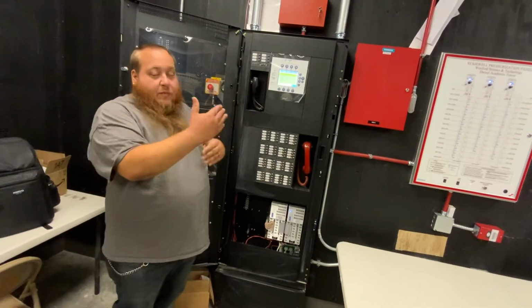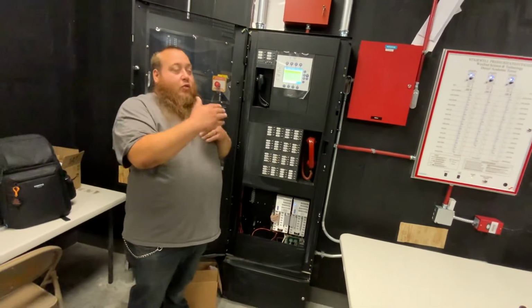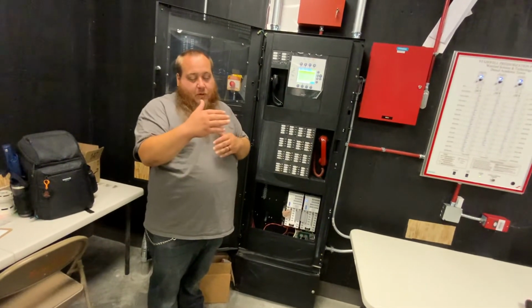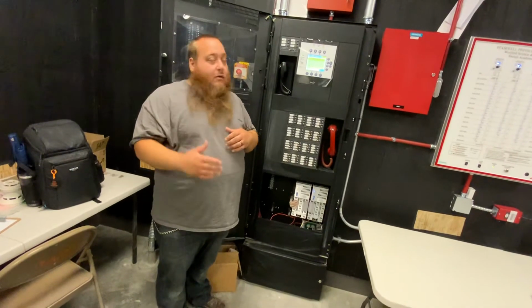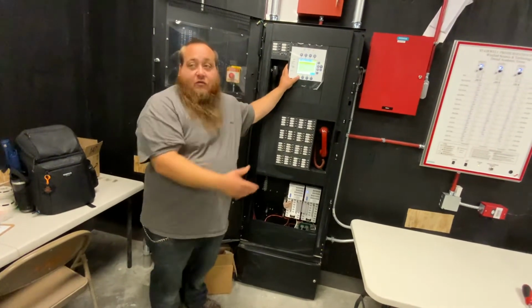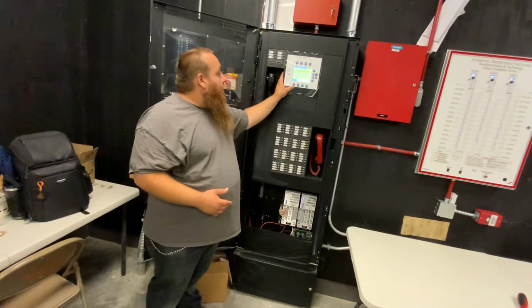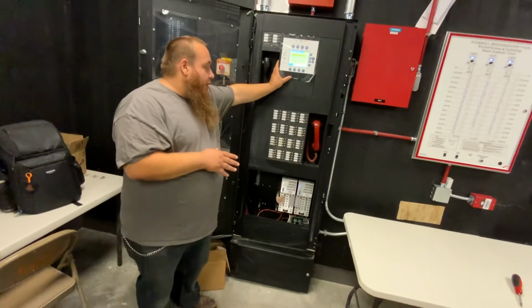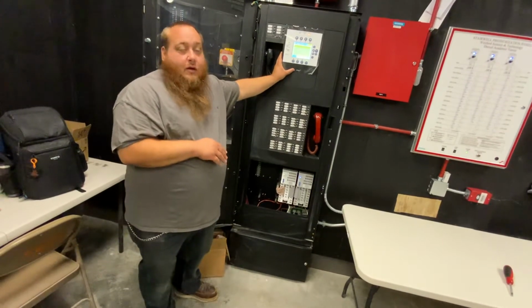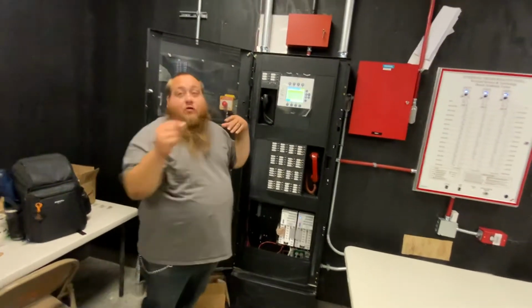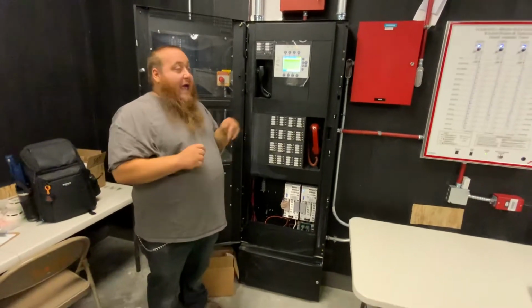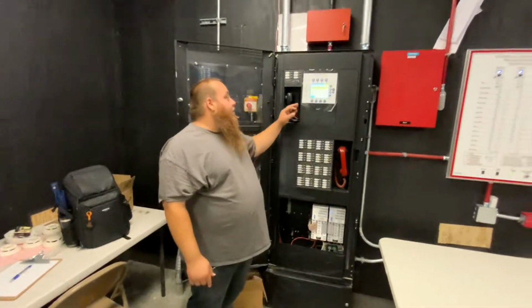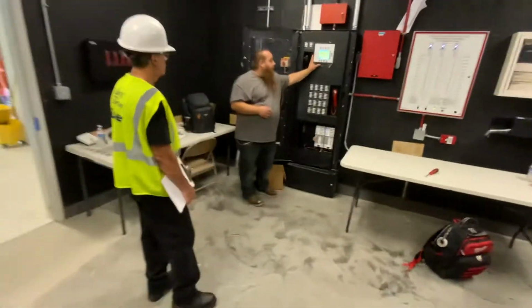Just in case you want to keep a pattern of, say, a ground fault, every time a door opens up, it hits a wire. It's easier to keep a pattern that way when you know things come in and out. Or when you know HVAC's running, you can find something. So that's the best part, how this system is fully self-aware. You can track things down a lot easier. And like I said, every smoke detector, pull station, duct detector, and relay has a number to it and a description. So everything attaches self-descriptive.